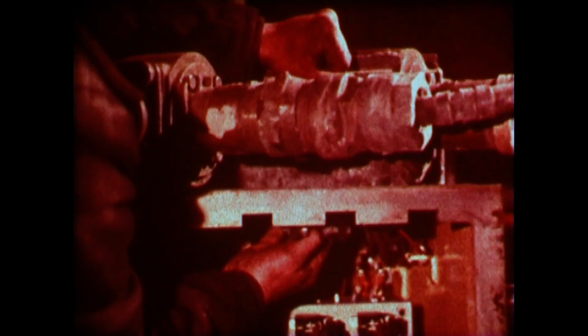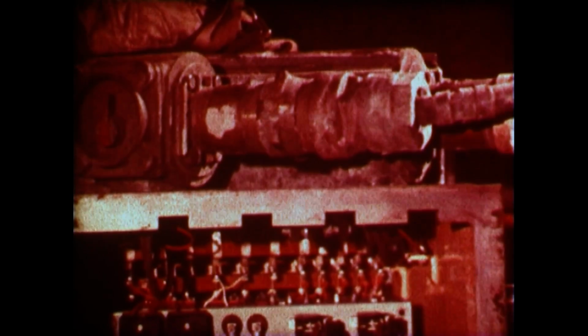I thought I'd check the gate end box, so I switched off the isolator and opened the door. To save time, I fiddled the interlock to bring the isolator back to the on position, so as to get the power back into the box with the door open. I could now see what relays were working and what was not, instead of spending time making separate tests. I could see the pilot relay was not working - it was bent in and not breaking contact.